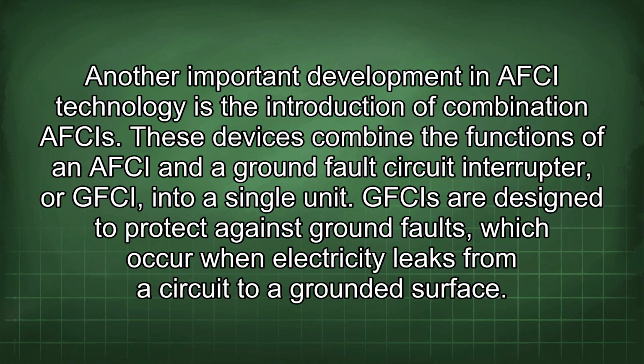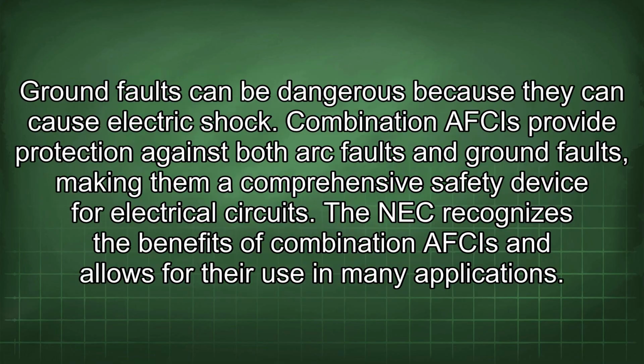Another important development in AFCI technology is the introduction of combination AFCIs. These devices combine the functions of an AFCI and a ground fault circuit interrupter, or GFCI, into a single unit. GFCIs are designed to protect against ground faults, which occur when electricity leaks from a circuit to a grounded surface. Ground faults can be dangerous because they can cause electric shock.